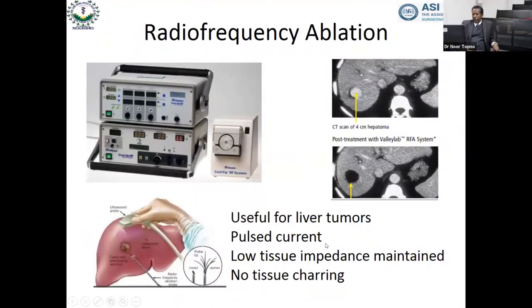Radio frequency ablation, here the current that is used is much, much higher. It is there obviously in the radio frequency range. That means it is somewhere above 500 kilohertz. It's very useful for liver tumors. Pulse current is delivered. Usually the tissue charring is quite less, and to bring down and maintain the resistance of the tissues in and around that area, cold water or cold saline is actually circulated through the needle tip. So it's called a cool tip technology.